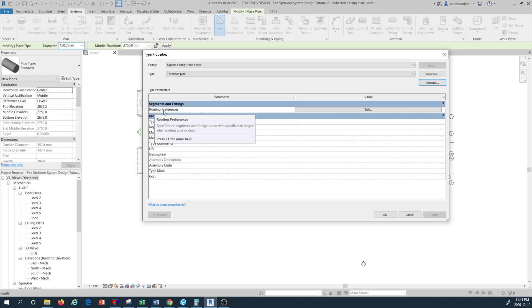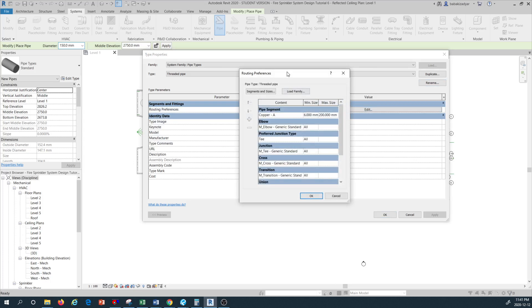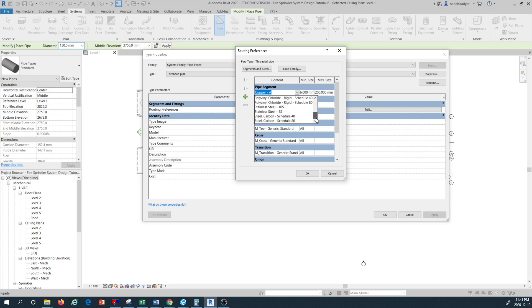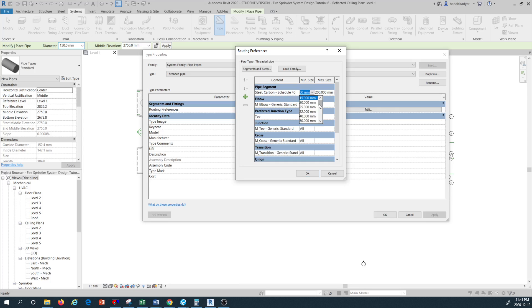The routing preference defines the specific segment fittings to be used to form a system. I'm going to click Edit. For this sprinkler system I'm going to change the pipe type from copper and go down to find Schedule 40 — steel carbon Schedule 40 — which I'm selecting.